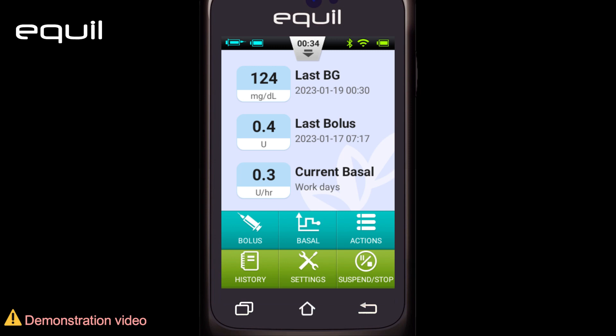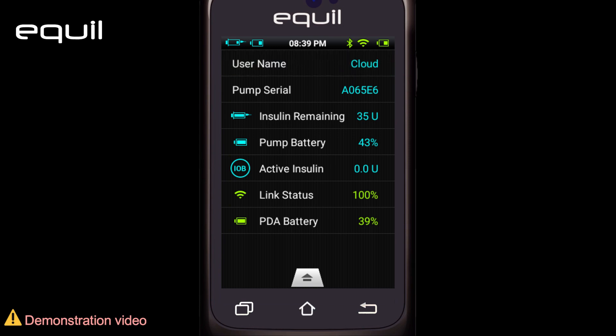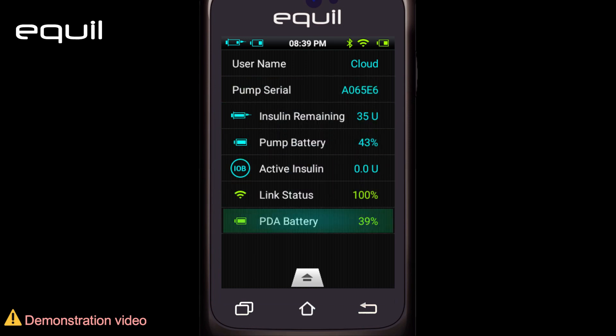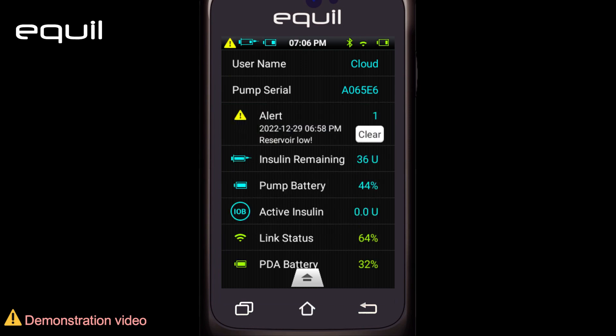Pressing the button in the middle of the status bar displays a larger screen with a detailed representation of the information in the status bar. It contains the name of the pump user and the pump serial number. Furthermore, all the data contained in the status bar is shown in numerical format, not only the icons. If there are any pump warnings, then we can acknowledge and cancel them from here.